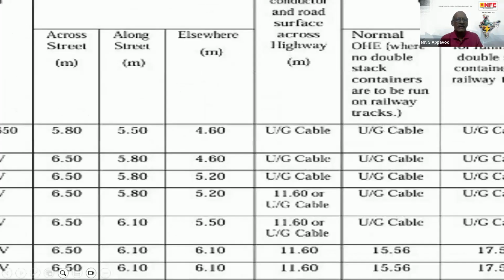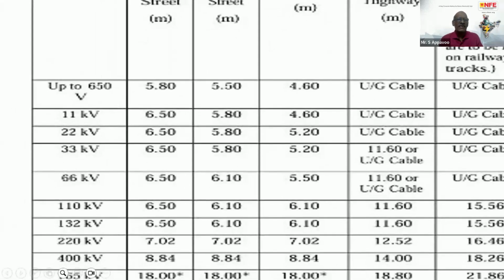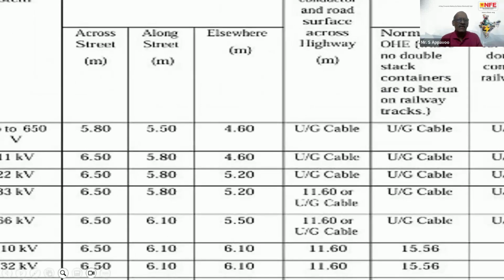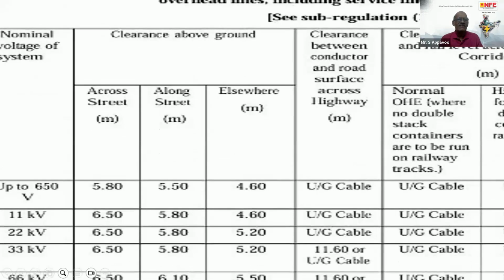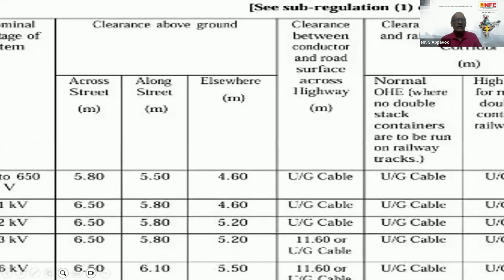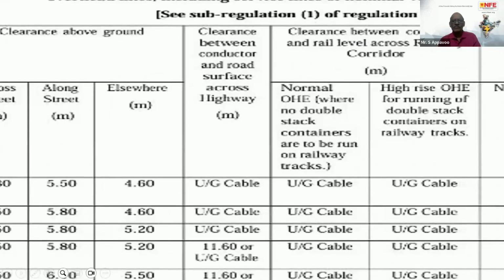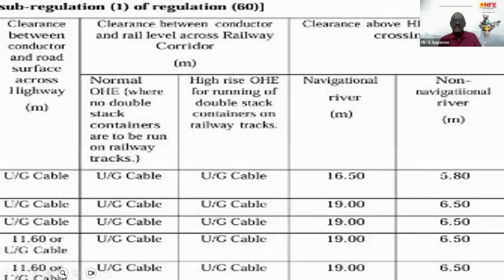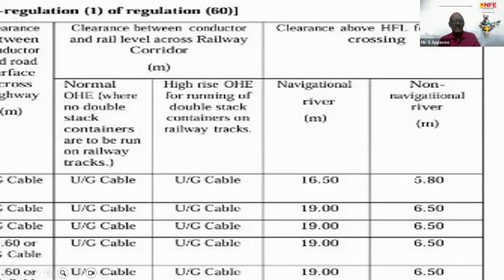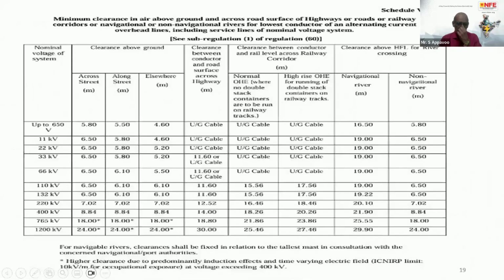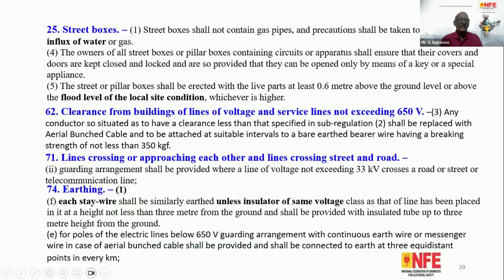For example, up to 11 kV, this is the clearance across the street. This should be the clearance above the ground. So along the street, this is the clearance. Elsewhere, suppose it is a place where people do not occupy, there is no street, no crossing or along, then this clearance is sufficient. So if it is for a navigational river and non-navigational, everything is clearly given in the regulation. The supplier has to provide it during the construction itself.